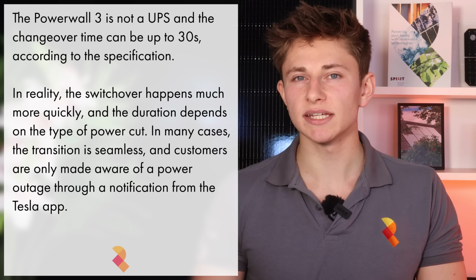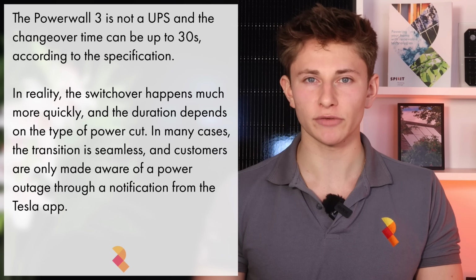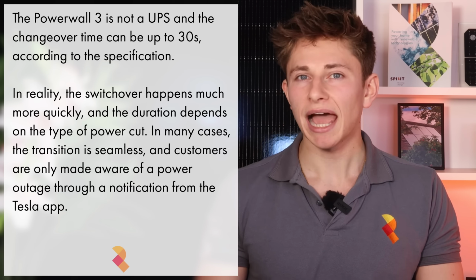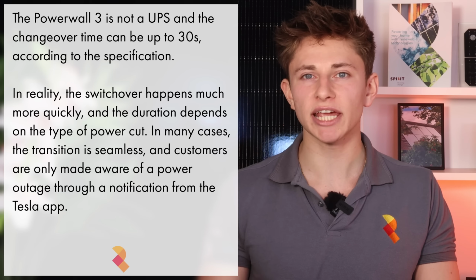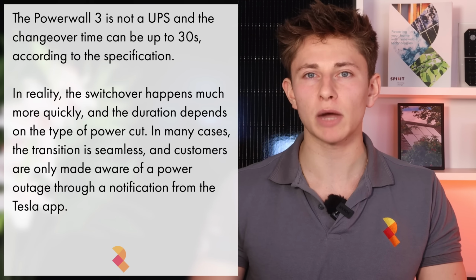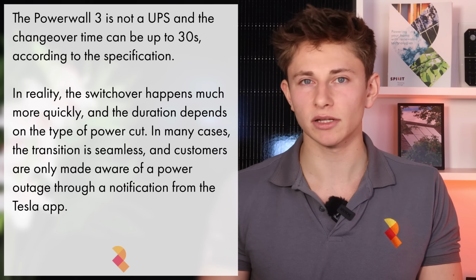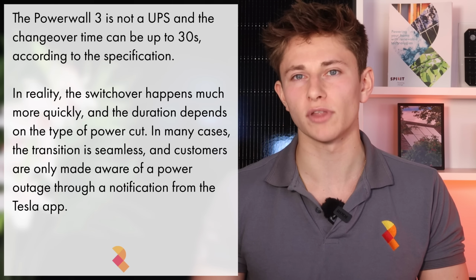On installation, the main incoming supply is routed through the gateway, and the gateway is then able to cut the line to and from the grid in the event of a power cut, thus islanding the house from the grid. The backup is not rated as a UPS, and the specified changeover time is up to 30 seconds. However, it's typically much quicker, and the changeover time usually depends on the type of power cut and how quickly the gateway can cut the line to the grid and take control of the load.